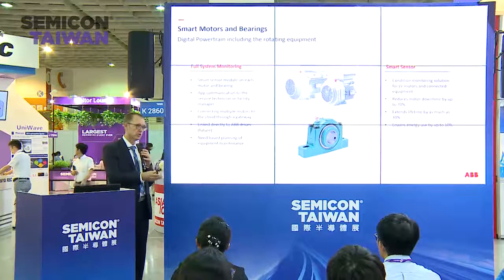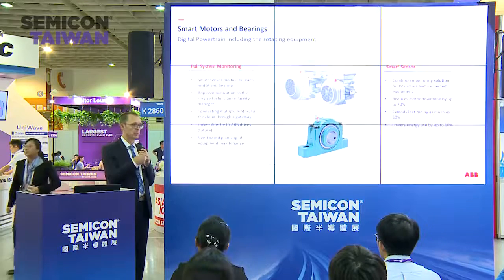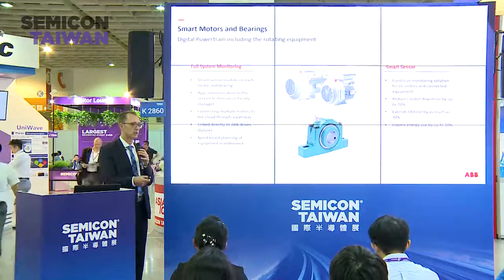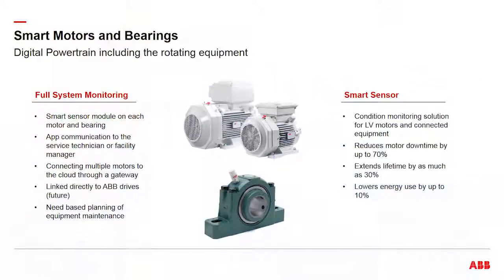Another benefit is that instead of lubricating bearings on a regular schedule, you now do it when the sensor tells you there's an actual need. In most cases this extends the time between maintenance, because on a fixed schedule you stay on the safe side—maybe only allowing it to run 80% of the time before re-lubrication. But based on actual operation, maybe it doesn't need that, and you can run 120% of the time, extending the schedule.